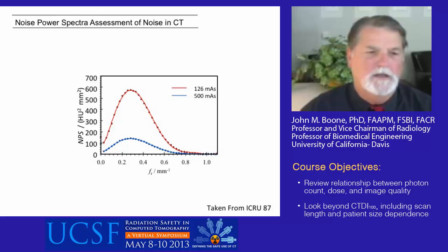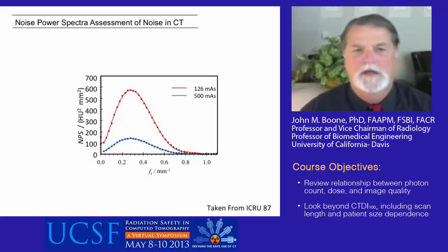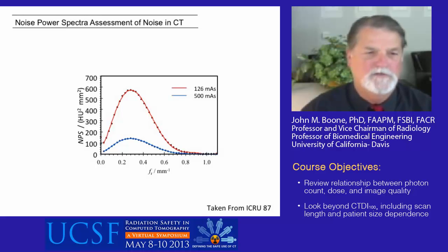And this plot illustrates that as you go to thicker slice reconstructions for the same acquisition techniques, you get lower noise levels as you would expect. We can also vary the dose levels used, and you can see that when you reduce the mAs by a factor of 4, thereby reducing the radiation dose by a factor of 4, the noise variance goes up precipitously as well.